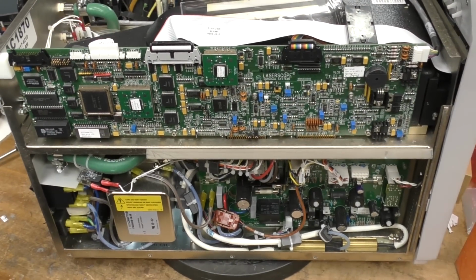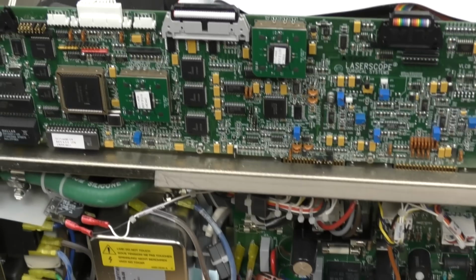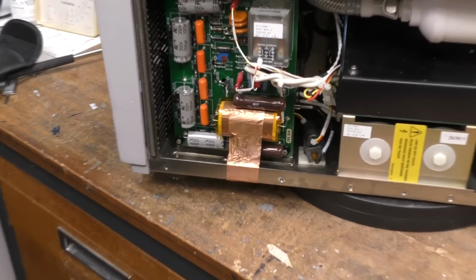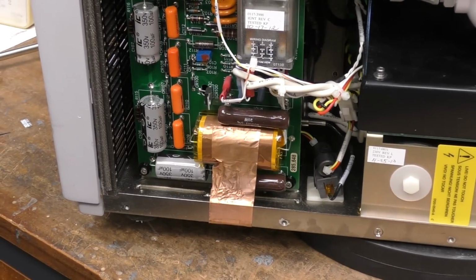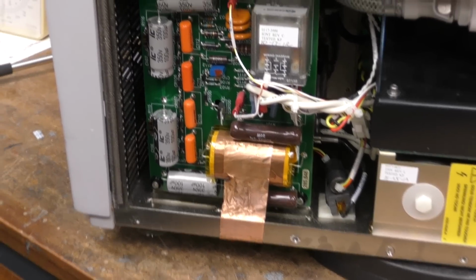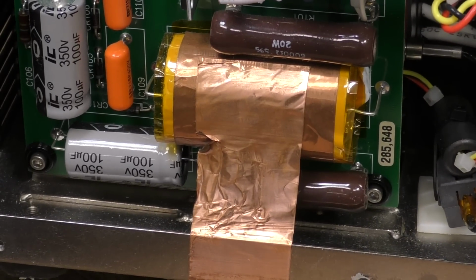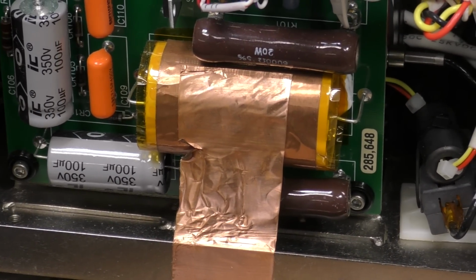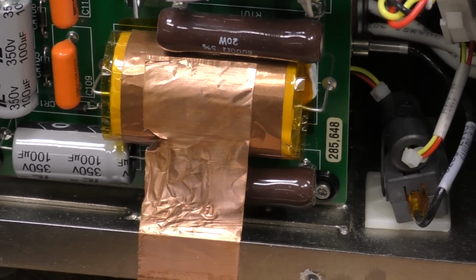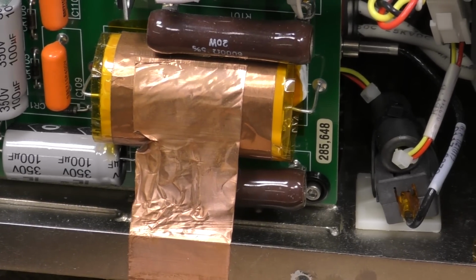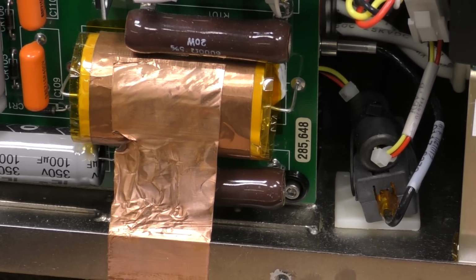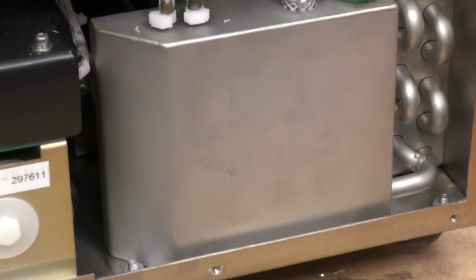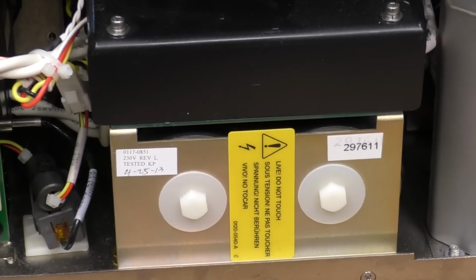So opening it up, we've got on one side what seems a slightly ridiculous amount of electronics, and on the other side some more power stuff. I would imagine this is probably to do with controlling the flashlamp. There looks like some high voltage stuff there, and some fairly serious shielding, strapping to probably avoid issues from the high voltage ignition pulse of the flash tube, because that'll have a very fast rise time, so that's plenty of scope for causing various electrical havoc. And here we can see this is the cooling radiator, the reservoir tank, and there's a few bits behind there we can't quite see yet.